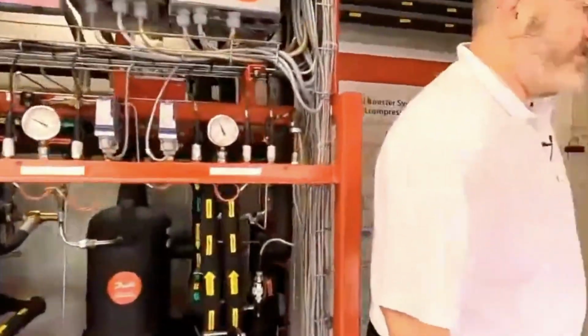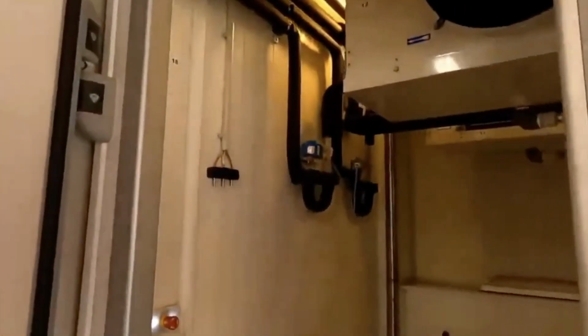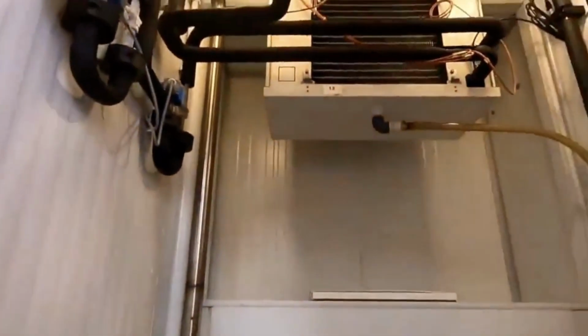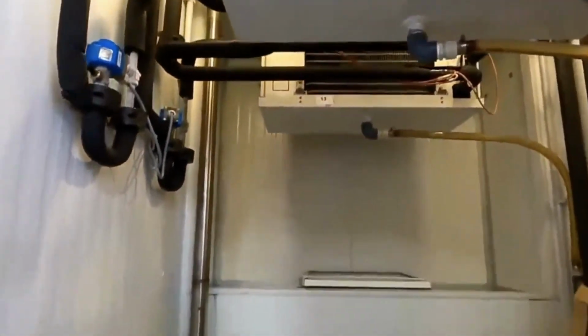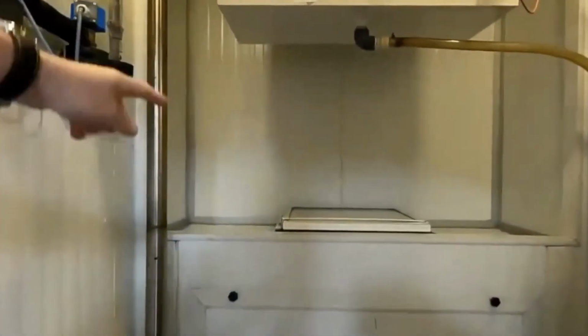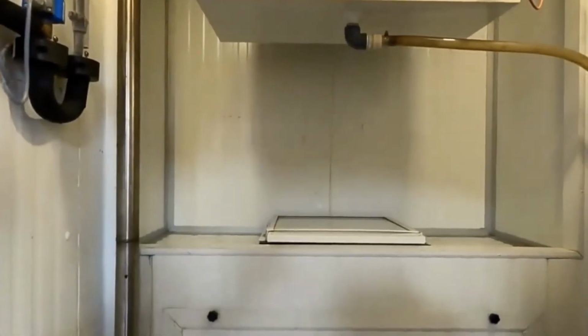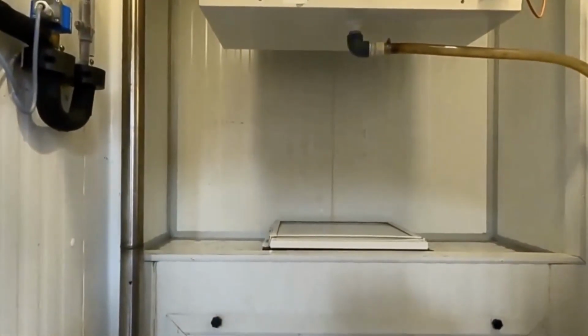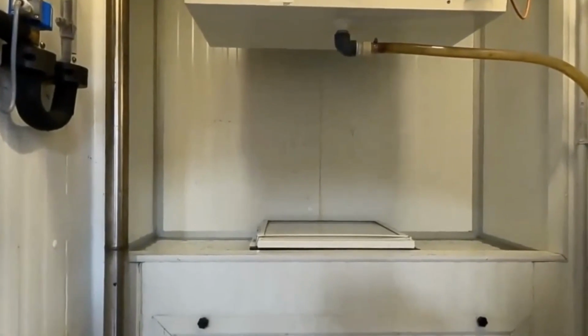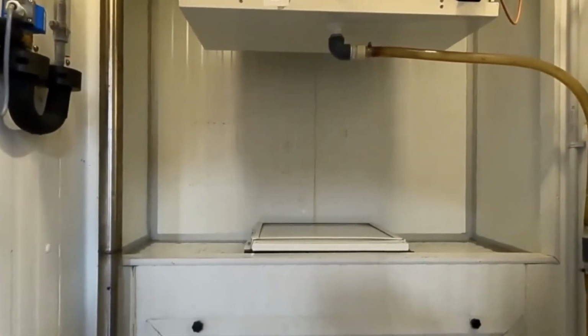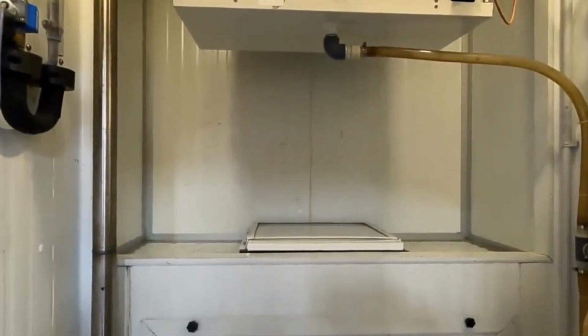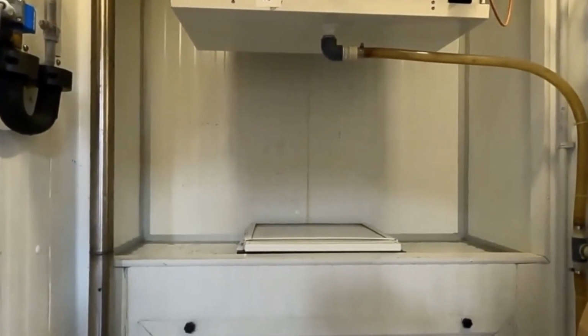this unit is serving 2 medium temp evaporators in our walk-in box here. And there's a shelf in the walk-in box. If you look here, there's a shelf. We use that shelf for a couple of reasons. One, to access the gas cooler, which is beneath it, but we can also open that lid and create false load by discharging gas cooler heat into the walk-in box to keep the system running in cold ambience.